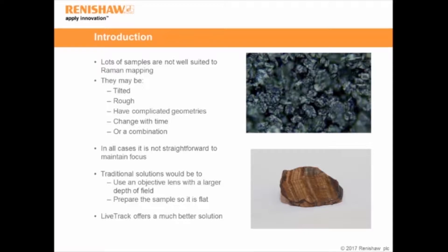In all these cases, it's not straightforward to maintain focus. The traditional solution would be to use an objective lens with a larger depth of field, which means going to a lower magnification, lower numerical aperture objective. While this is fine, because we're reducing the numerical aperture, we also sacrifice Raman intensity and spatial resolution — so at a cost of mapping these samples, we're actually losing quite a bit of our performance.